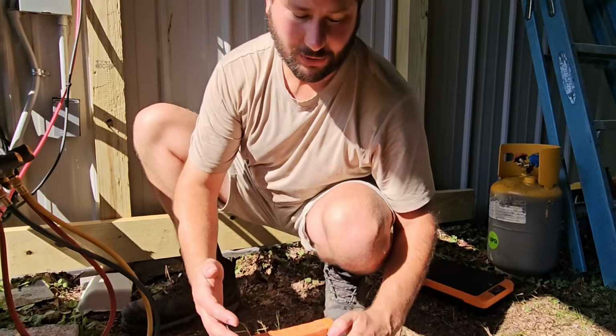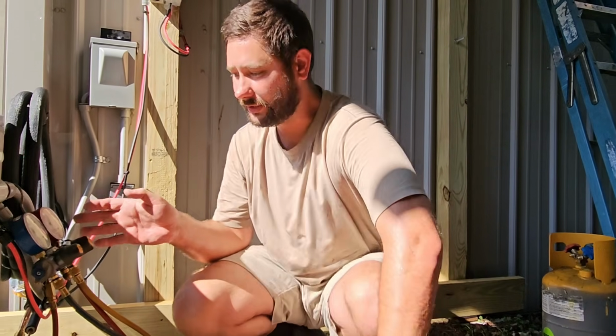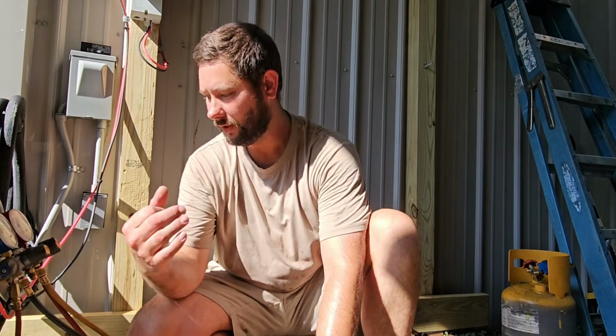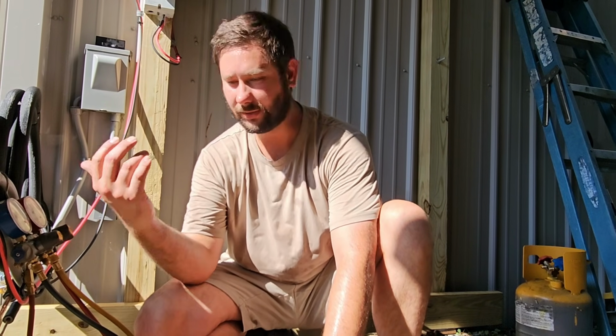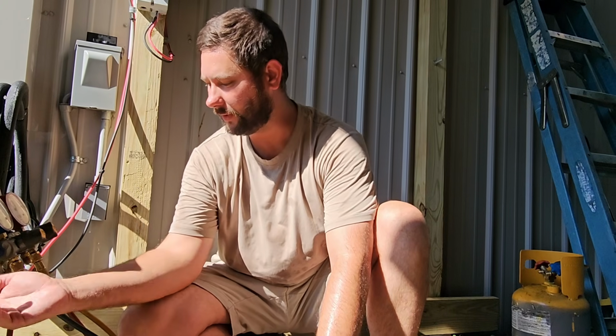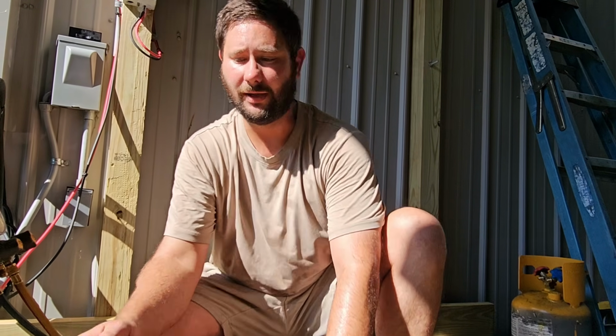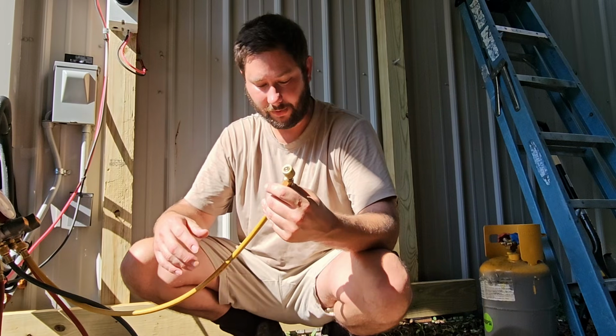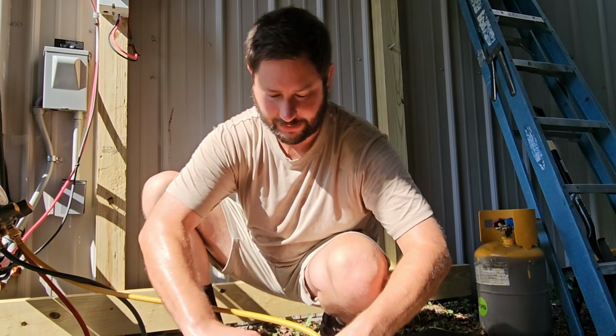You want to be able to monitor your vacuum. You can look at your gauges, and you can actually get a micron gauge. A micron gauge, you can attach it to the pump, or you can attach it to a port on the unit from the furthest point from where you're pulling, and that will help you to monitor your vacuum level. Now that our nitrogen is almost out, we're going to connect it to the pump.